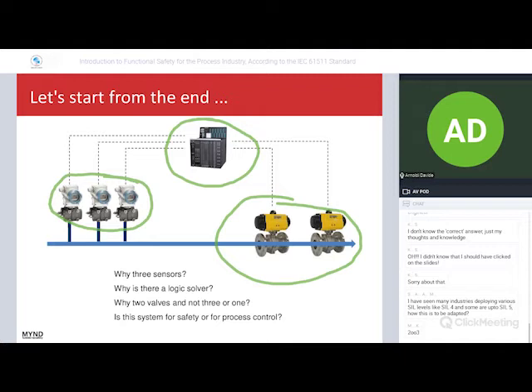The final question is: is this system designed for safety or for process control? Those are good questions. Everything is designed using the functional safety standard IEC 61511. It is the only way to justify why we have to use 3 sensors instead of 1, instead of 2, instead of 4.